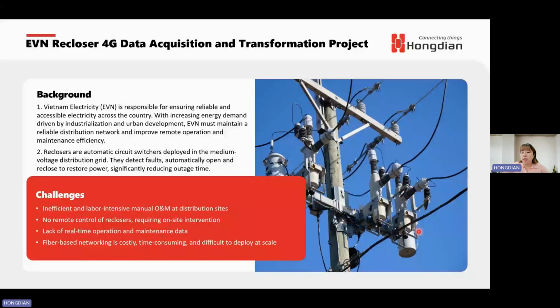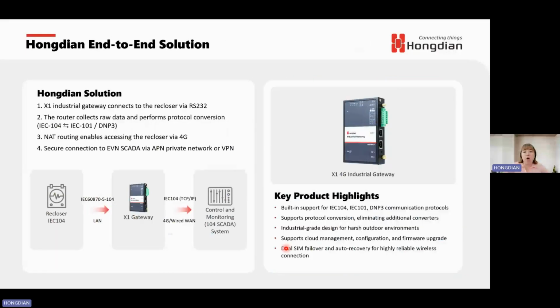However, EVN faces several challenges: manual inspections were time consuming and costly, these reclosers could not be remotely controlled, and the lack of real-time data made grid monitoring very difficult. Therefore, we offer them our X1 gateway. It helps EVN achieve remote monitoring and control of the recloser, connecting directly to the recloser, collecting field data, and converting it into the required format for the control center.